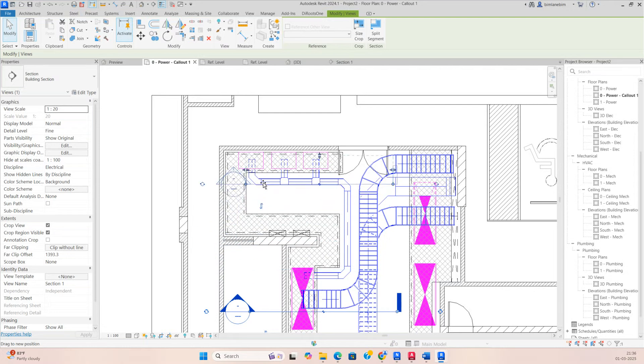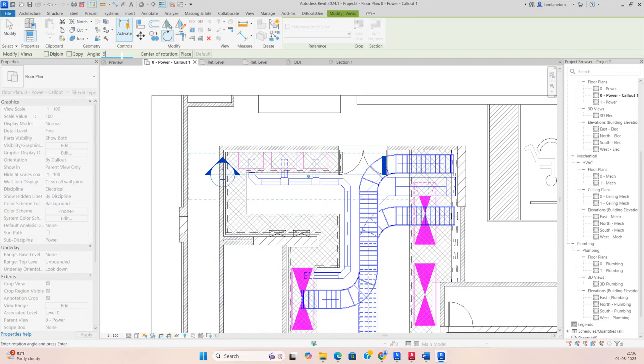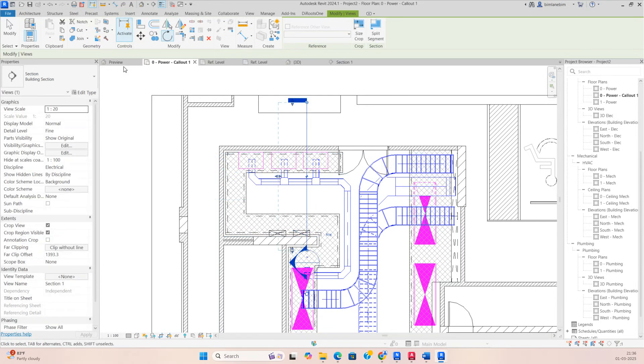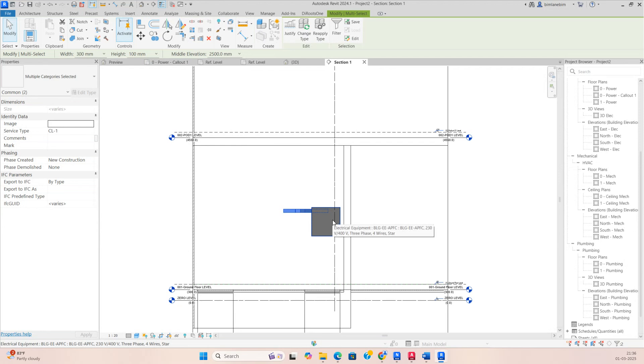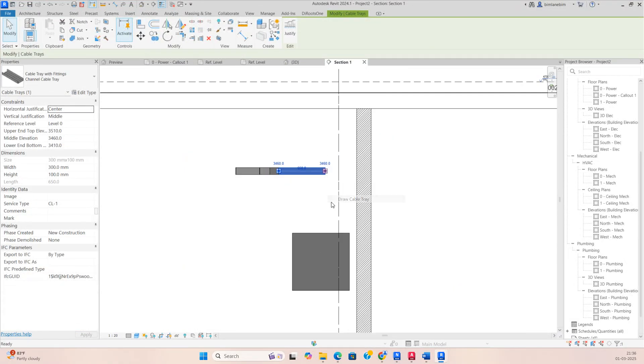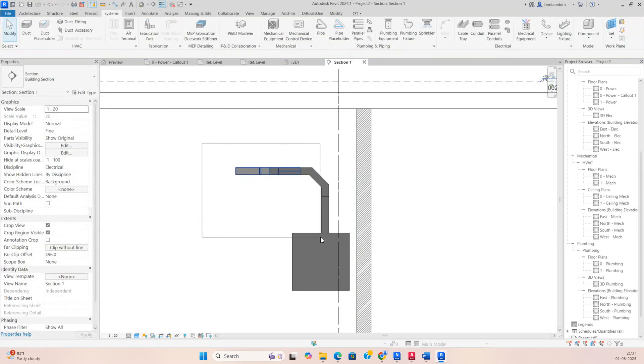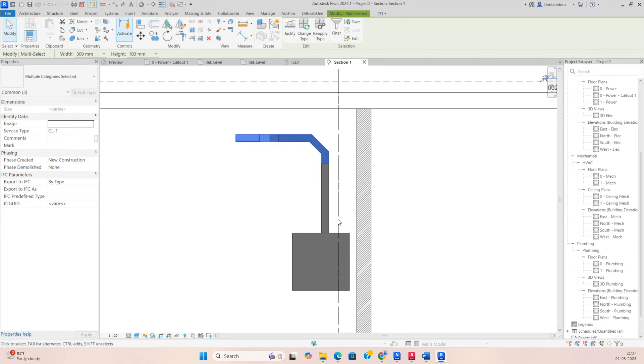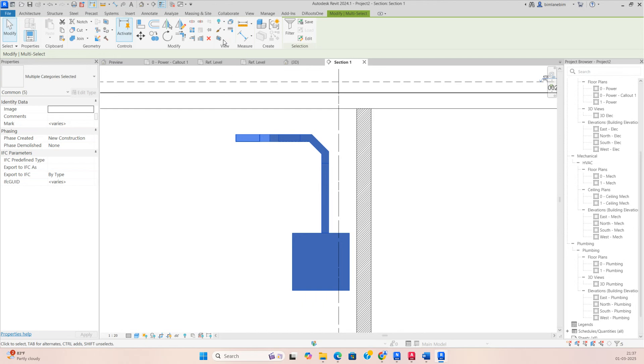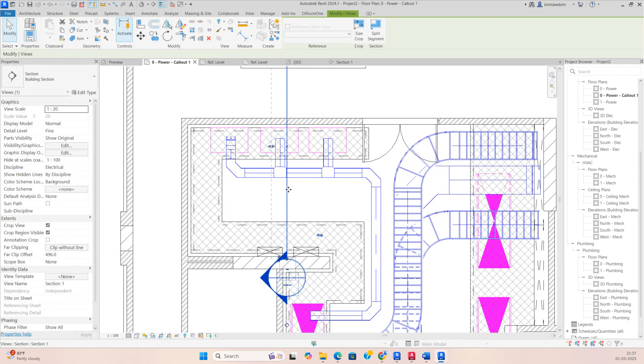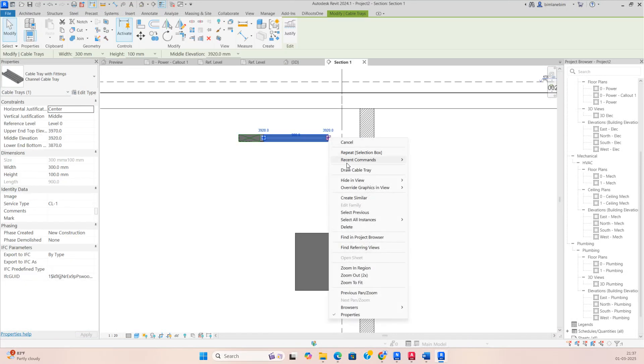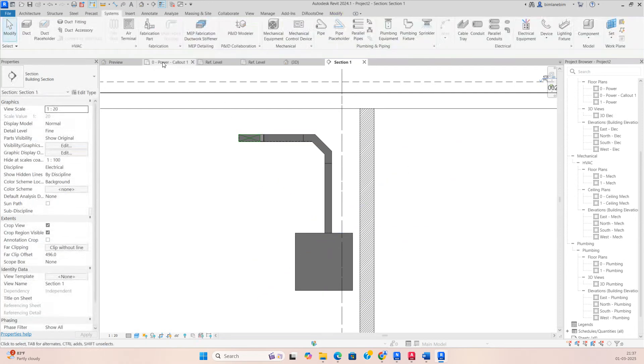For each panel, create a section, move it to the panel location, and rotate the section 90 degrees. Go to View and draw the cable tray, dropping it down to the panel. You can see this in the 3D view. The same method applies to each panel — draw and connect the cable tray down to the SMDB panel.